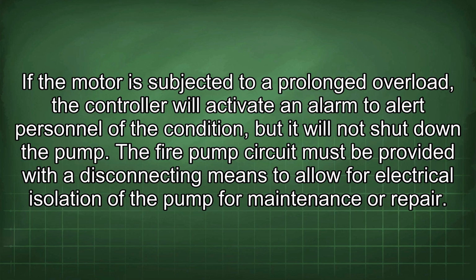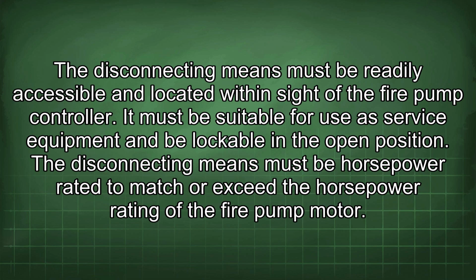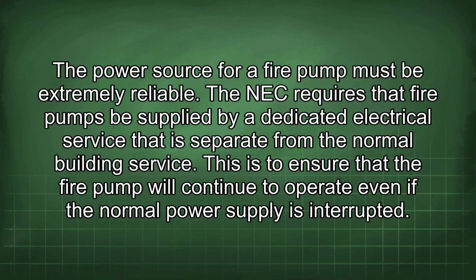The fire pump circuit must be provided with the disconnecting means to allow for electrical isolation of the pump for maintenance or repair. The disconnecting means must be readily accessible and located within sight of the fire pump controller. It must be suitable for use as service equipment and be lockable in the open position. The disconnecting means must be horsepower rated to match or exceed the horsepower rating of the fire pump motor. The power source for a fire pump must be extremely reliable.